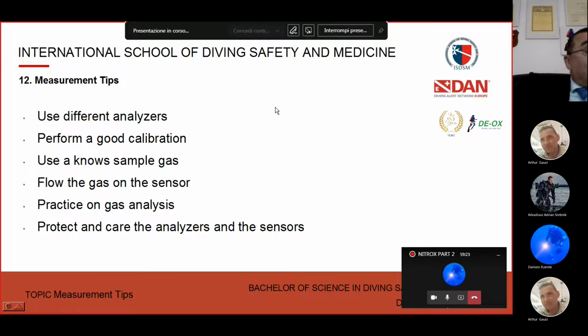Flow the gas on the sensor, give the right flow, don't exceed. Never make the error of putting the analyzer close to the valve and then opening the valve - that may blast and destroy the sensor. Always turn on the valve gently and then put the analyzer on the valve.